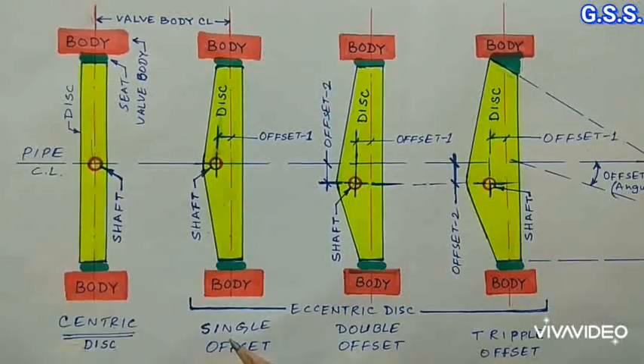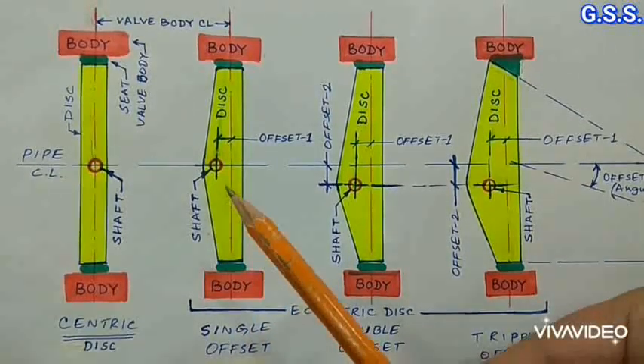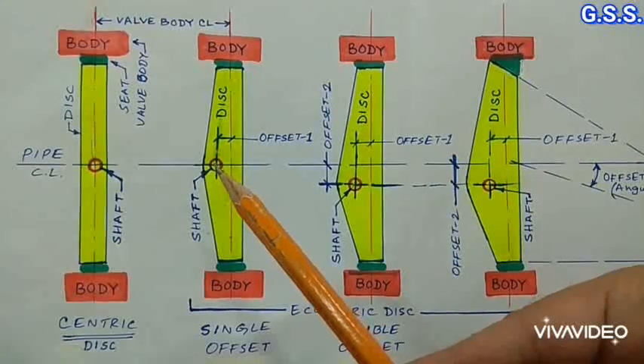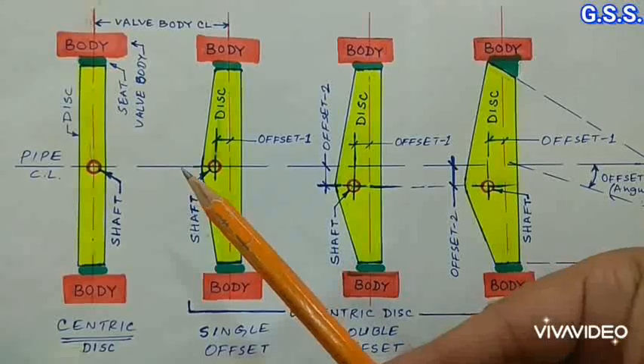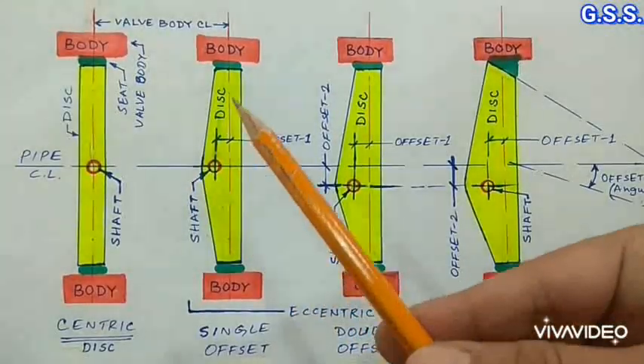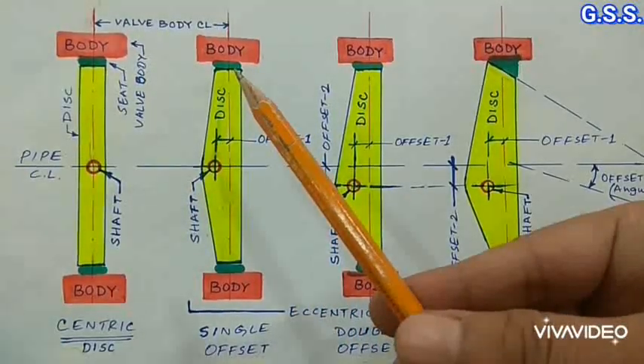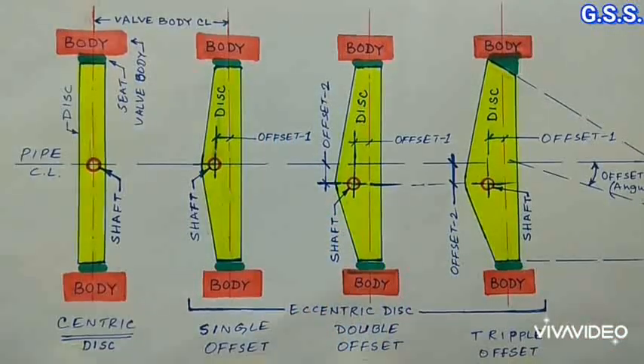In single offset eccentric butterfly valve, there is an offset between shaft axis and disc axis along pipe center line. This provides continuous sealing surface on the disc with less rubbing of disc with seat.